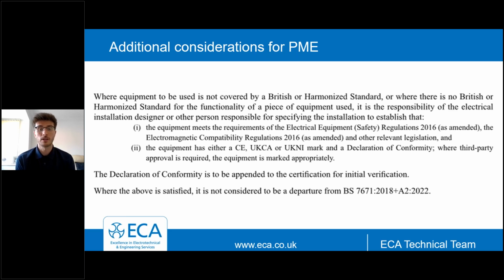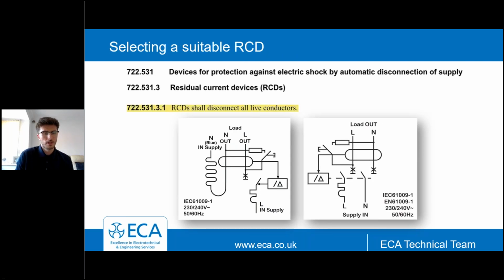Some of these installations are then going into service, and it's then being discovered at a later date that this hasn't been achieved, which of course would be non-compliant with the regulations and introduce a potential risk to the installation. So we stress to members, ensure that you're carrying out and having these conversations with the manufacturers if required, obtain this information and attach it with the relevant certification as part of the initial verification process. Okay, so that covers PME outdoors.